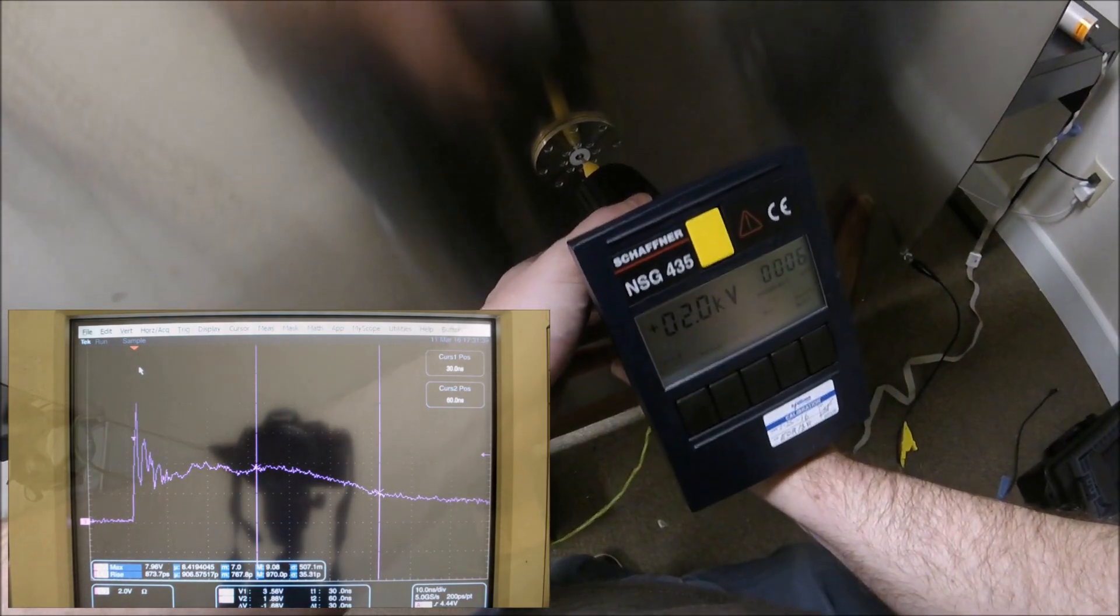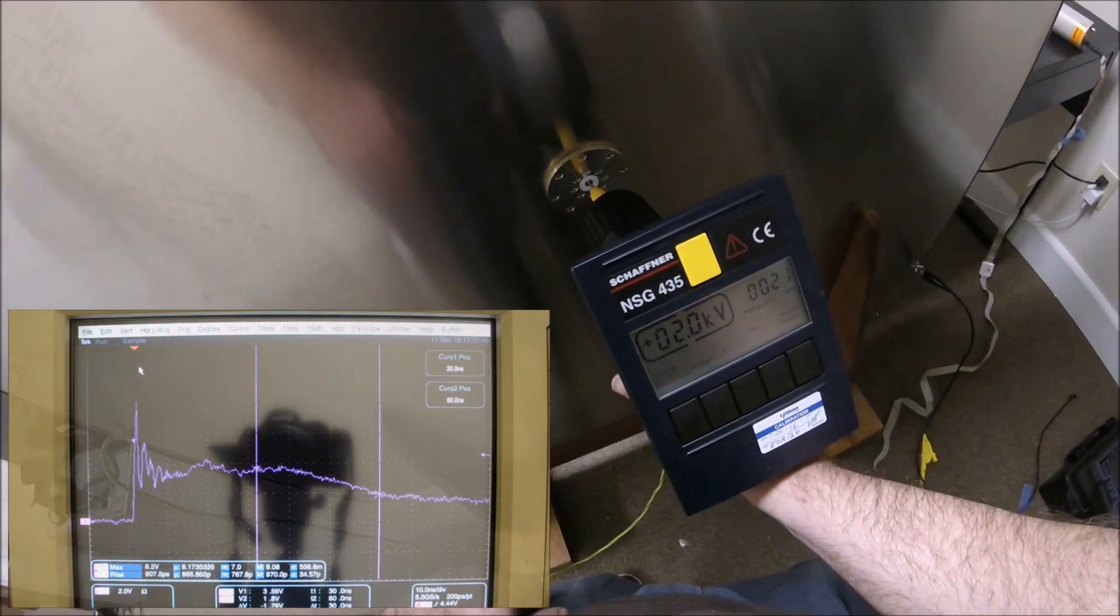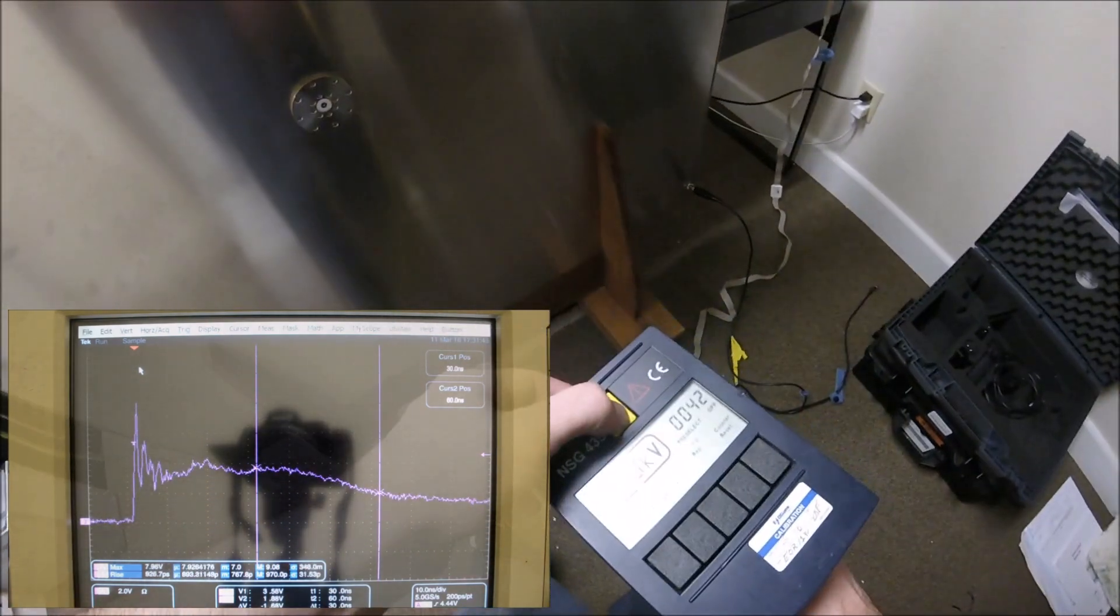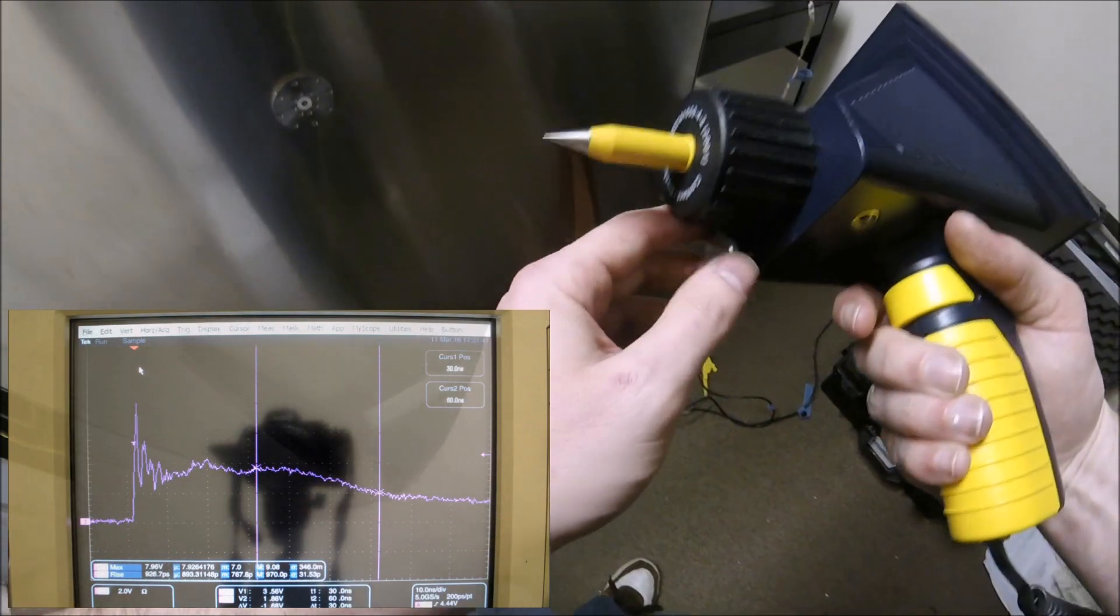We'll program the unit for 20 Hz. Keep in mind, we're going to circle around and do the same thing at 8 kV, the highest level for contact discharge immunity in the IEC standard.